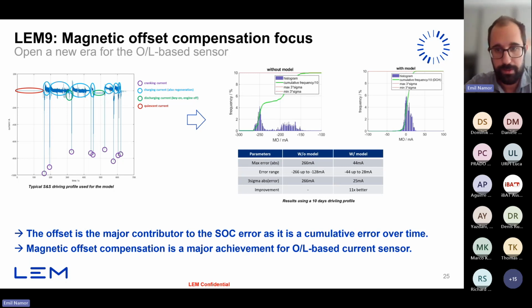This breakthrough, this particularly low offset that this sensor is able to achieve, is thanks to software embedded in this ASIC that aims at compensating the magnetic offset that the ferromagnetic core of these sensors introduces. By doing this, we are able to considerably reduce the offset that the measurement of the sensor has, and that is a major element that must be considered when using a current measurement for a state of charge computation.